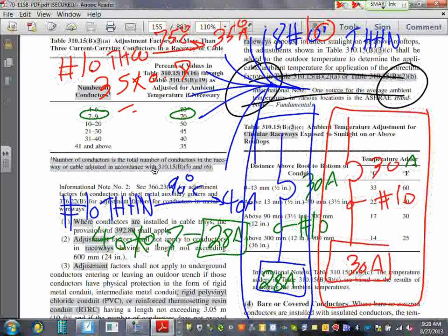24.5 amps. Now your system is completely going to change. Now your system is 24.5. This is number 10. This is 25, the next step in overcurrent device, based on the insulation of the conductor. The reason why this doesn't play a big deal in real life, guys, is because we're always indoor, we're using THHN anyway. That becomes a big deal when you take your conductors outdoor when you're using THW.